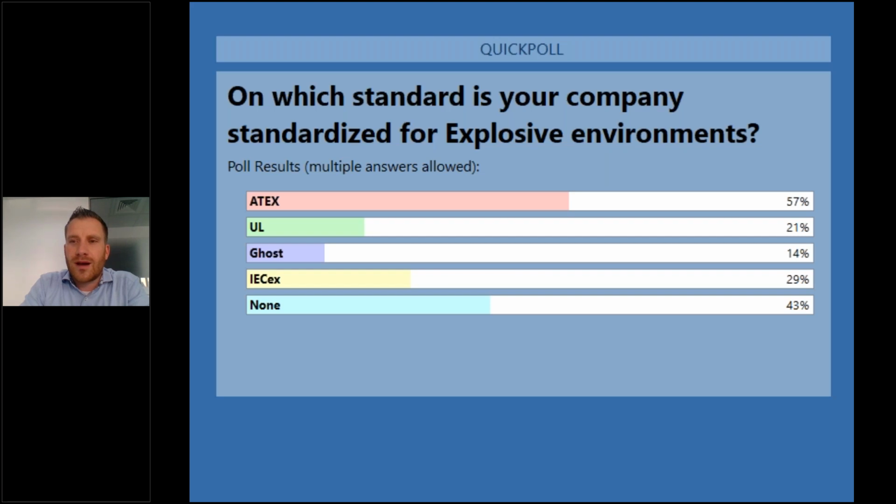Also IECEx is a trend which has become more and more active in recent years. It's not really a directive, and maybe this is something we will discuss in a different session, but it's mainly a standard, and IECEx and ATEX can apply together in a certain country. As I mentioned before, ATEX is law, so not only IECEx will be applicable, but ATEX still needs to be fulfilled. So in many cases we see a combination of the two.